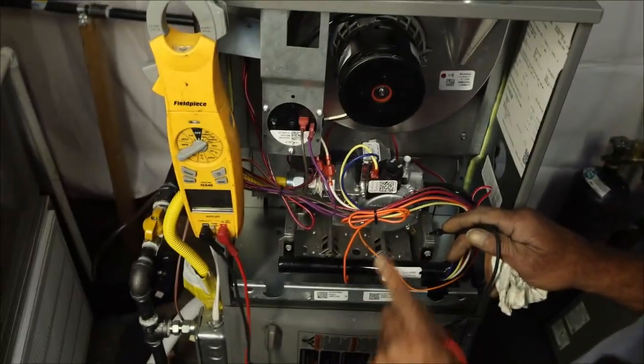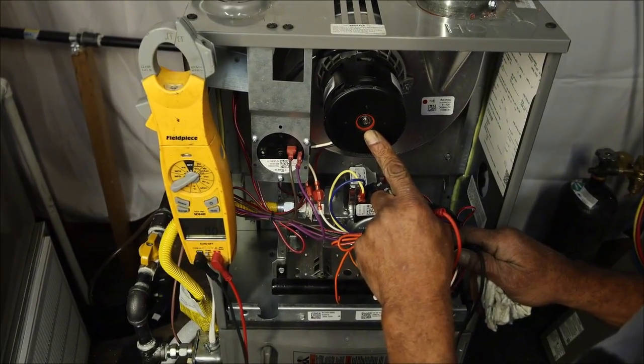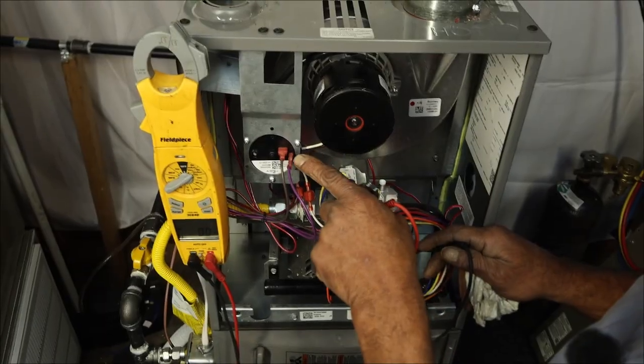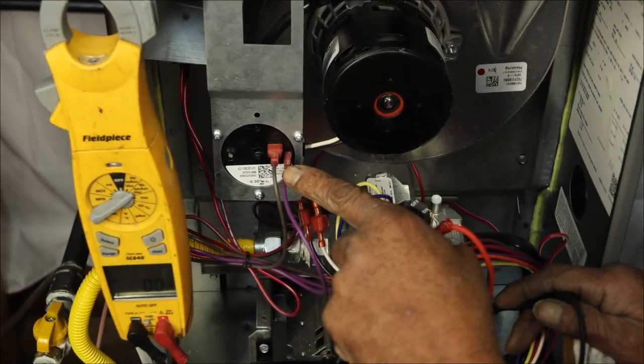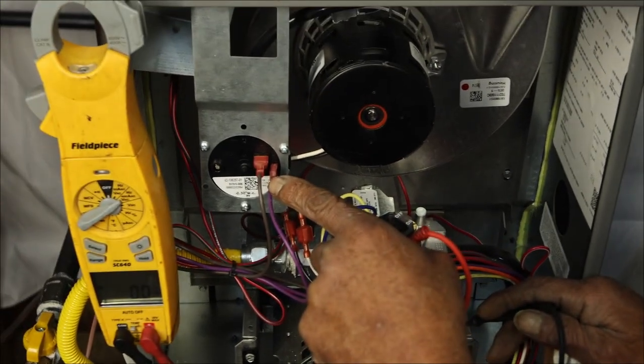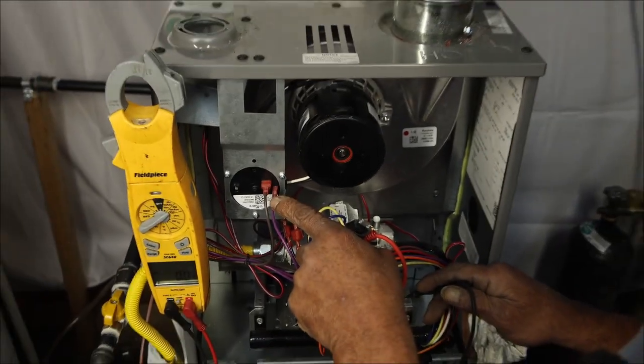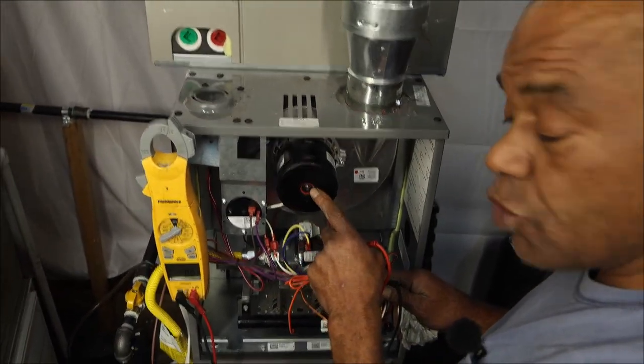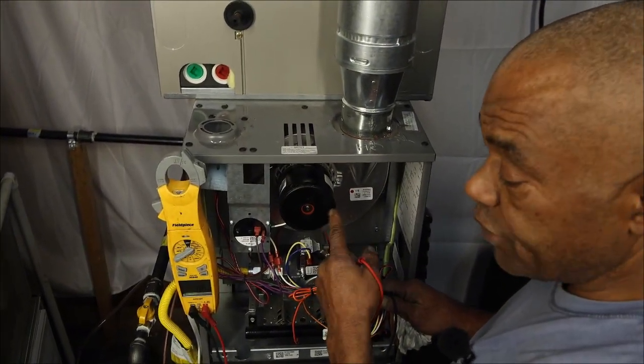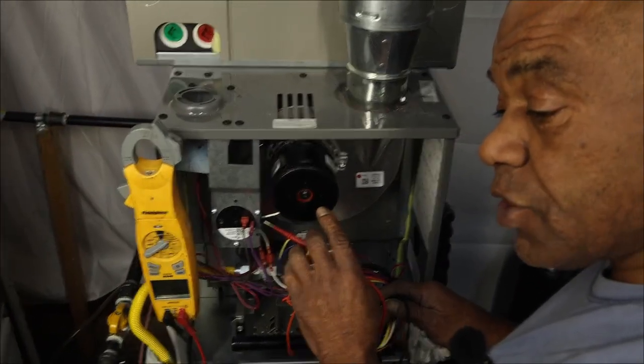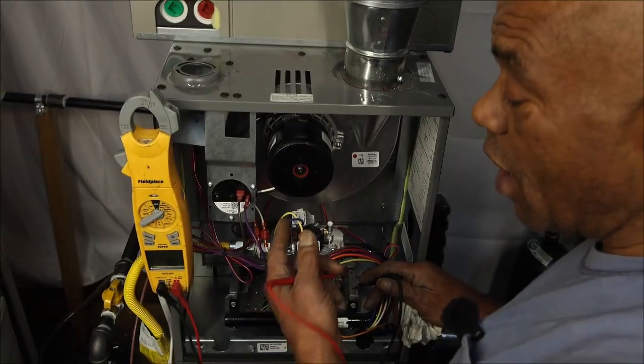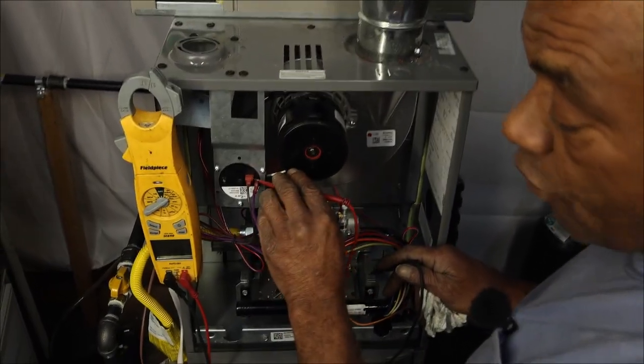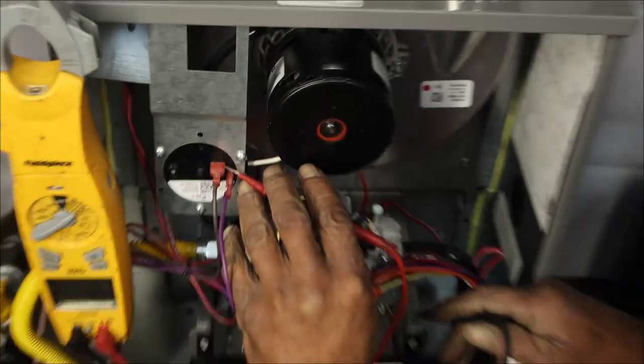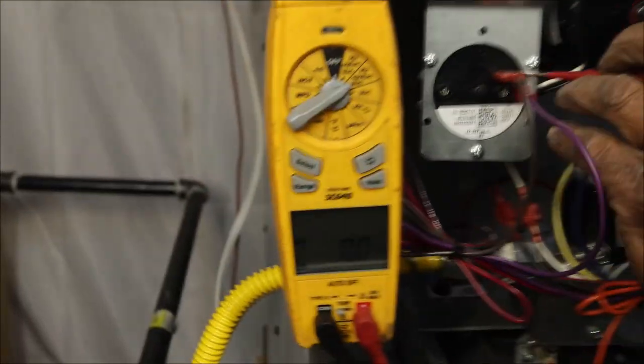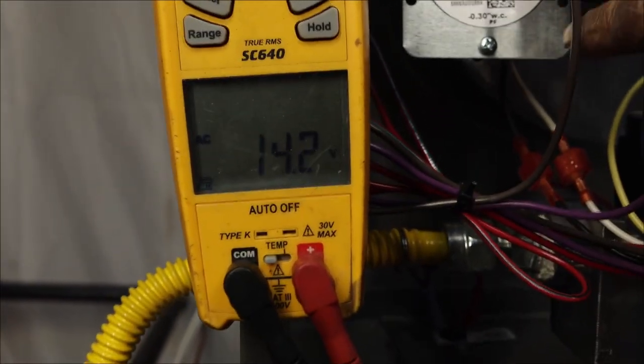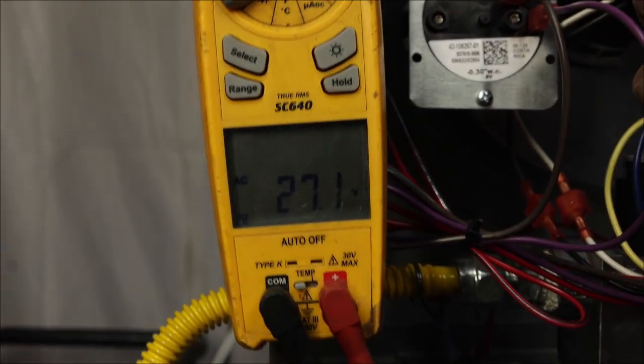When the circuit board sends power to the induced draft fan motor, it's also simultaneously going to send power to the pressure switch. And it's going to wait for that power to come back to the circuit board in order to prove that the induced draft fan motor actually served its purpose. So what we need to do, I'm going to shut the unit off, and then I'm going to turn, well, it's starting back up right now. So right now, if I look at my amp probe, if I get a good connection, I'll see that I have power coming in.